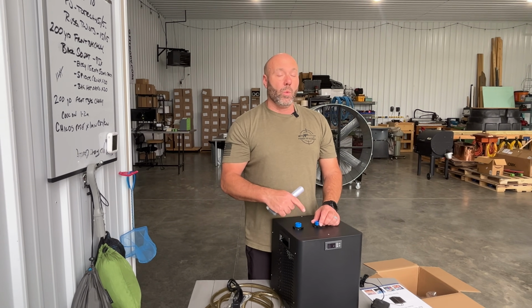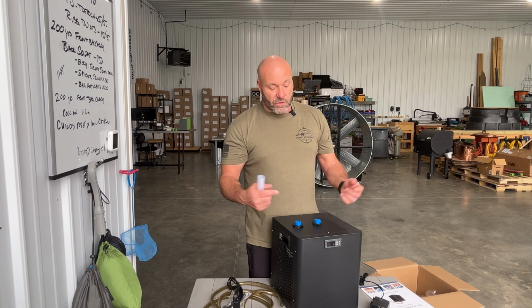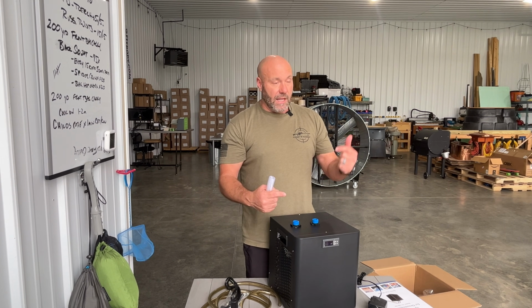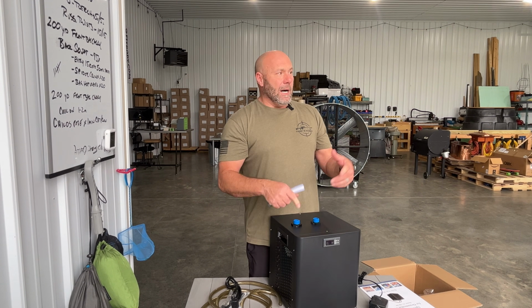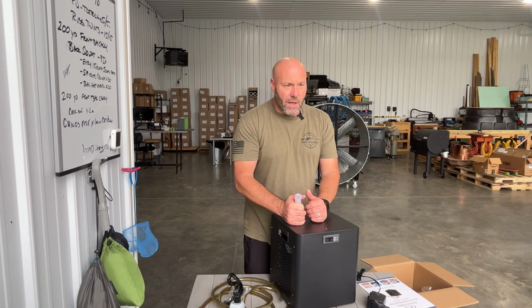Again, this does not have a pump in it. You have to have a pump to push or pull water through it. Otherwise, if you just hook this up to a cold plunge, port in and out, you will just freeze the unit. The other thing is, it's not big enough.